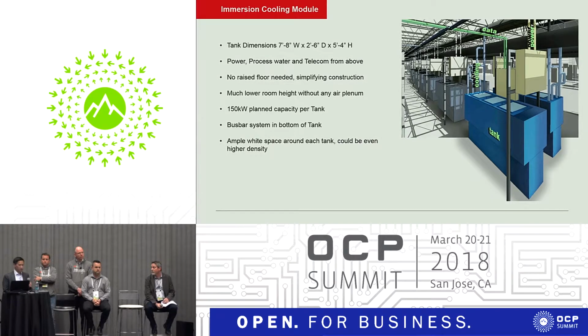And as mentioned before, for this particular study, we have agreed on 150 kilowatts per tank. And this is being delivered with a proprietary busbar system, very much similar to the OCP busbar system, however modified to go into the tank with a much higher voltage AC. We have rectifiers inside the tank, which are then transforming it to DC.